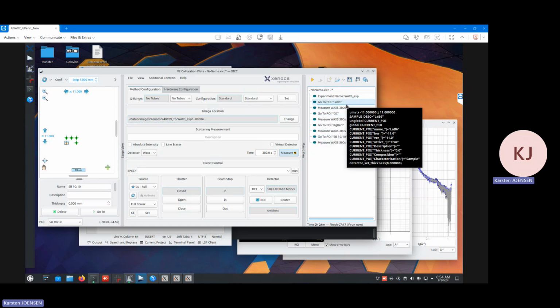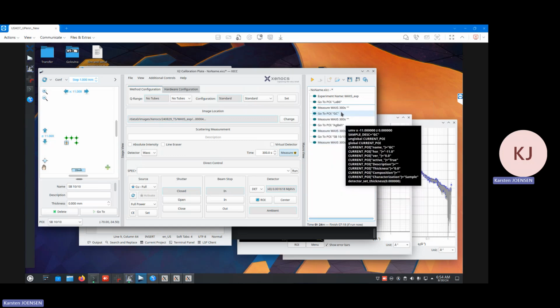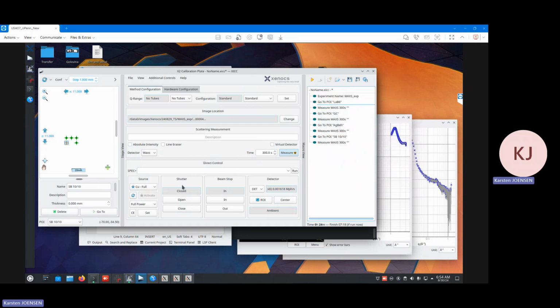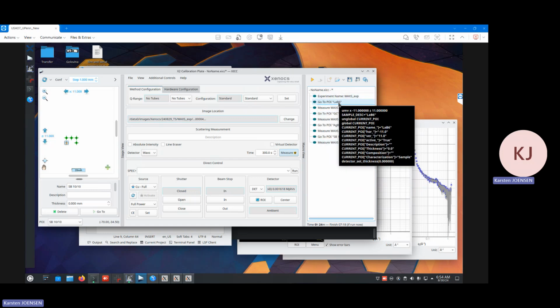What I will do is use the LaB6 to check the calibration, alter the calibration, and then show you how to use that calibration value in XSACT to correct the calibration for these 3 other ones. I'll also show you how to change the parameters. Let's say we had done the LaB6 before measuring the others. Once we have the calibration parameters, it's also possible to change them, and then they will automatically get entered into the header for the next sessions.